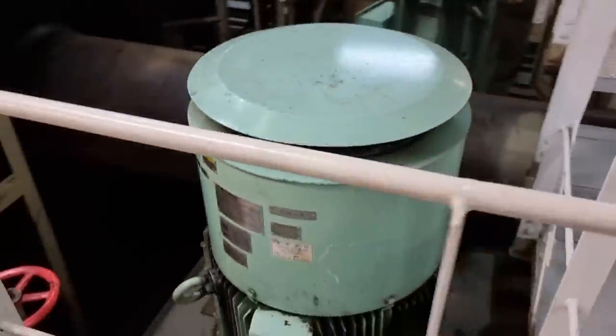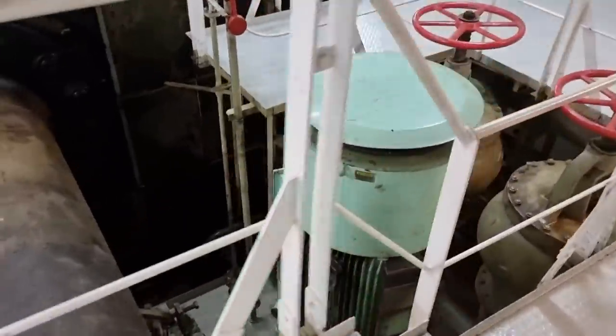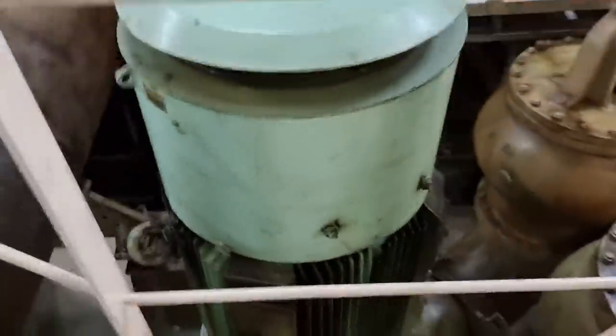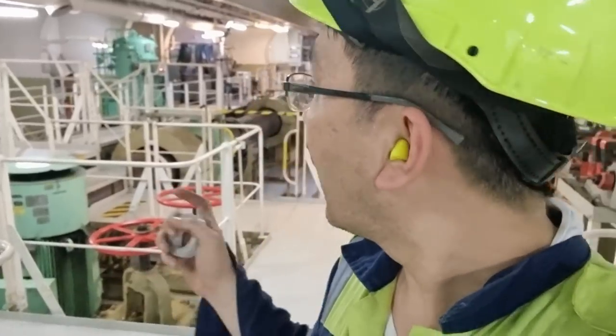I have decided to go down and check the condition of the terminals of our motor. We have two main lube oil pumps and this one is having a problem. I will check the windings line to line, line to ground, if everything is okay. Then if everything is okay, we need to lift up the motor and check the pump, if the pump is okay or there's something with the coupling or whatsoever. I will do the winding check on the motor.